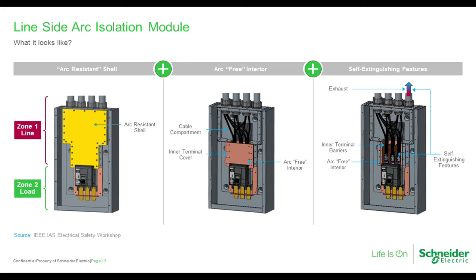If we remove the pressure cover and look inside, we see the cable vault in the center image, showing the incoming power cables and the thermoset polyester power connector surrounds. These are designed to maintain a maximum degree of separation between the power connectors, both phase to phase and phase to ground. They effectively emulate an IEC arc-free design, which reduces the chance that an arc can be generated in the first place. However, going further than IEC arc-free design, this design is performance tested per C37.20.7 and is also reliably self-clearing. We'll talk about how it works in more detail on the next slide.